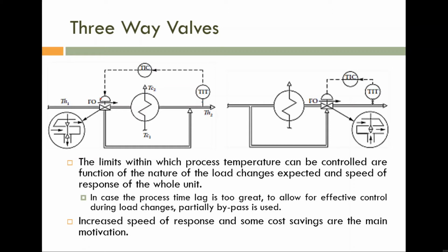If the system has a large time lag, then what is the problem? Why are we using integral action? Integral action is used to reduce the offset error, and the process will have a large offset error if it is affected by disturbance. So think about the situation where the process is regularly affected by disturbance. Then definitely we need an integral action. Am I correct? But we can't use integral action if the process has a large time lag.